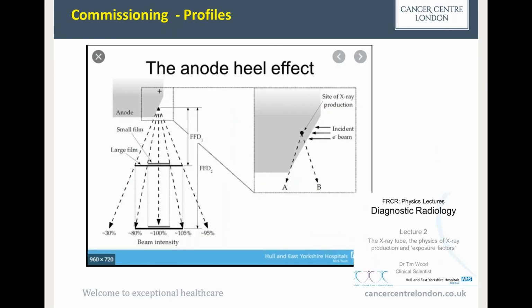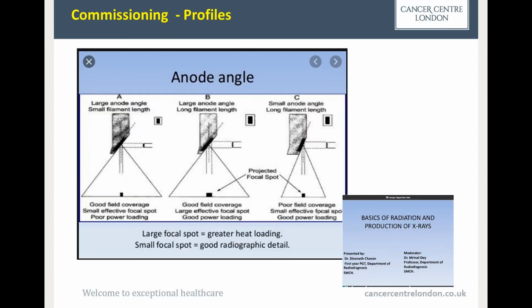Going ahead, as a one-off part of our commissioning, we also tried to see how profiles behave, because as is known, for X-ray units where the source of radiation is an X-ray tube, we have a heel effect. It means that partially radiation from the anode side can interact with the anode material, so from that side the intensity can be lower. It is most visible in diagnostic radiology, but it can be compensated by a specific choice of anode angle and also focal spot size.